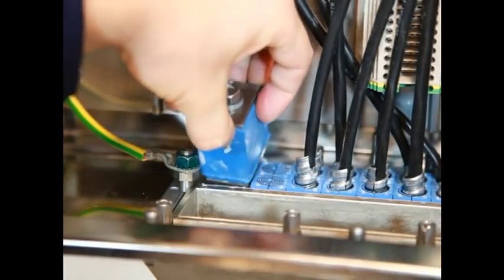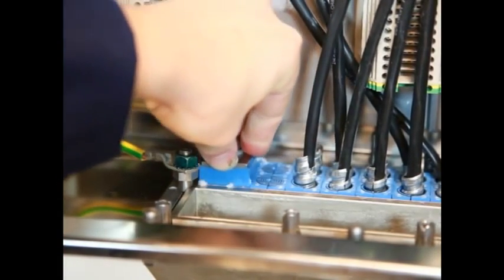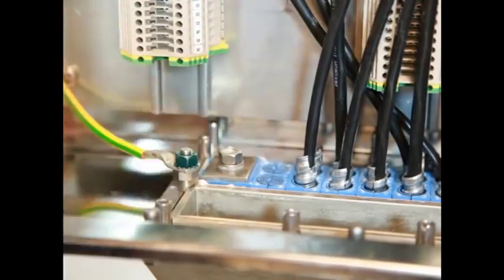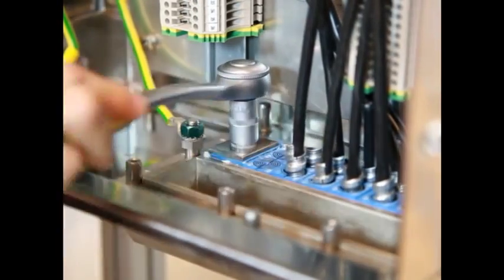Lubricate the Compression Unit on all sides. Insert it from the inside of the opening until stop. Tighten the compression unit to seal the frame. Check that the ground lug is correctly installed.